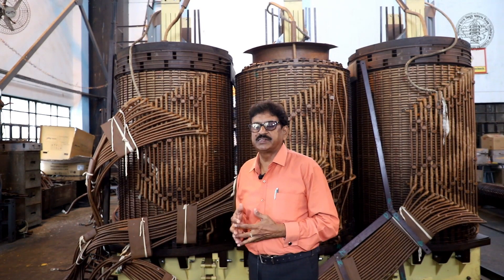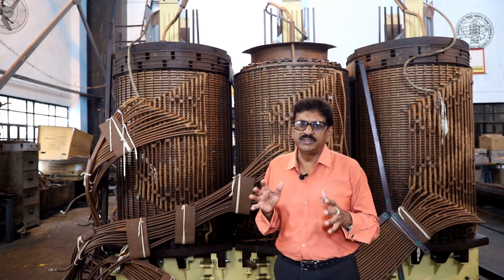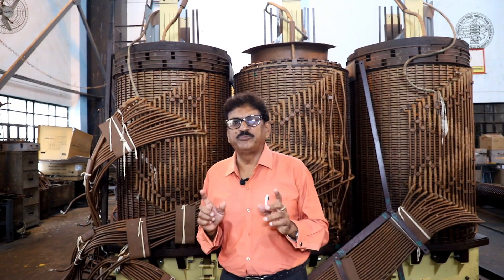We measure the winding resistance and the transformer turn ratio. We measure the open circuit test, which gives the magnetizing current. We also do a short circuit test, a magnetic balance test, and measure insulation resistance. After all permissible limits are verified, it is decided that this transformer is ready for dispatch. We give that information to our higher authorities and the process is complete.